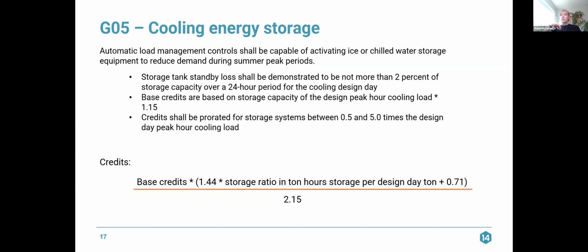Cooling energy storage. Automatic load management controls are required to be capable of activating ice or chilled water storage equipment to reduce demand during summer peak periods. So again, this is a shift, not a shed. I don't know why I feel so passionately about that.